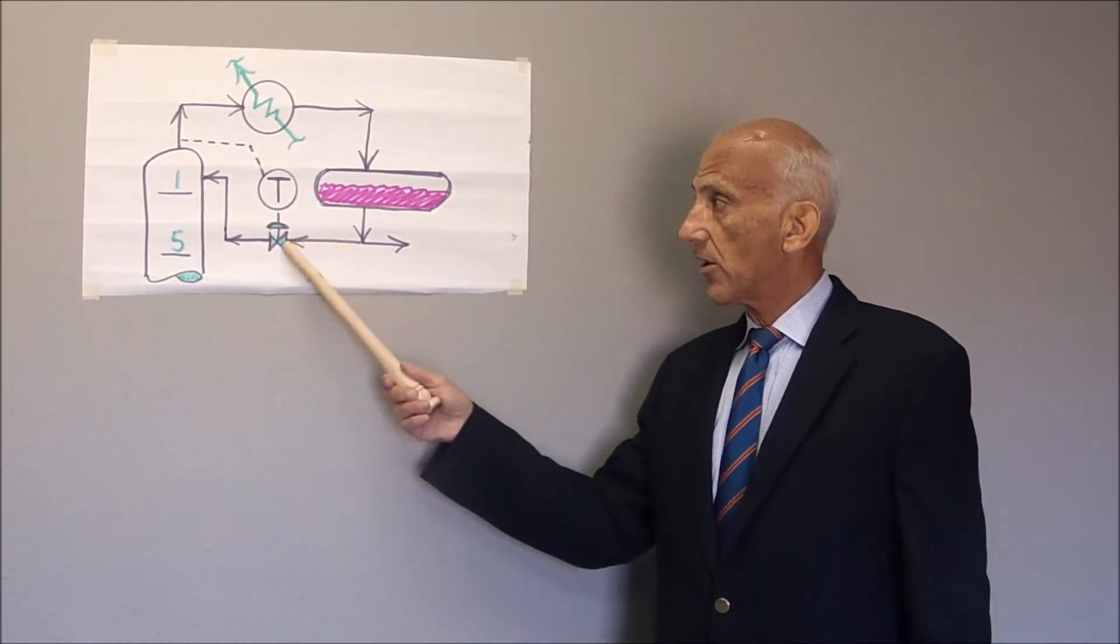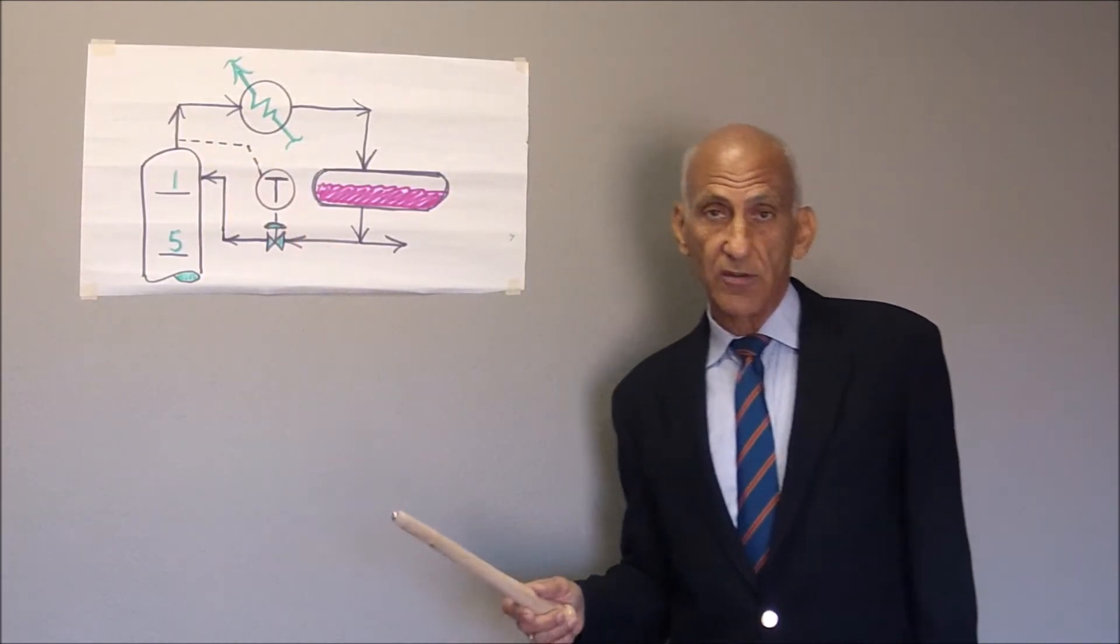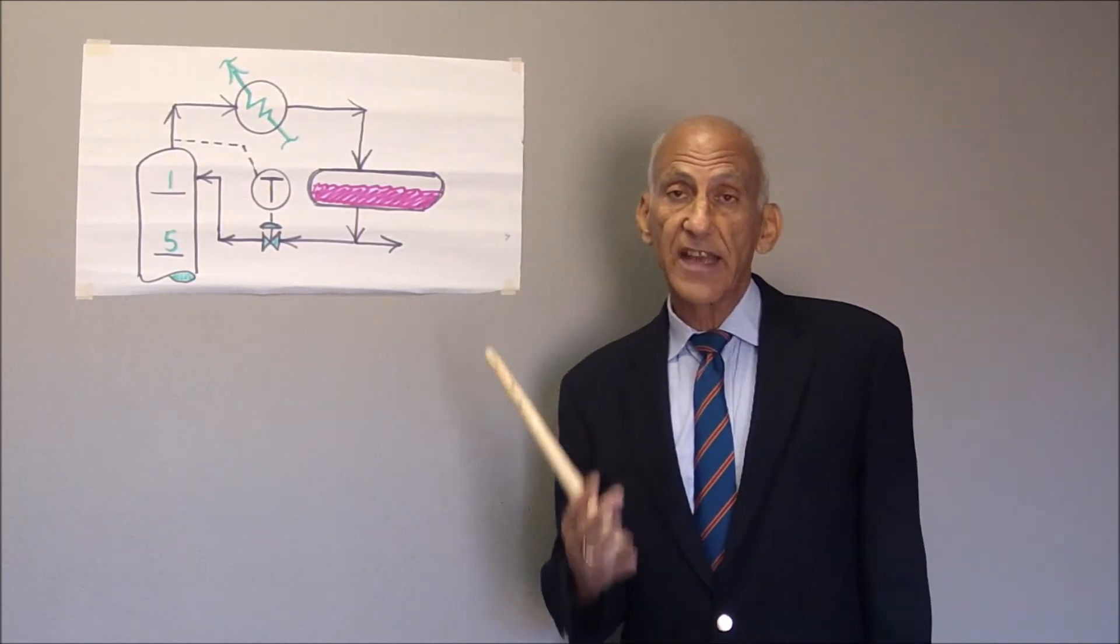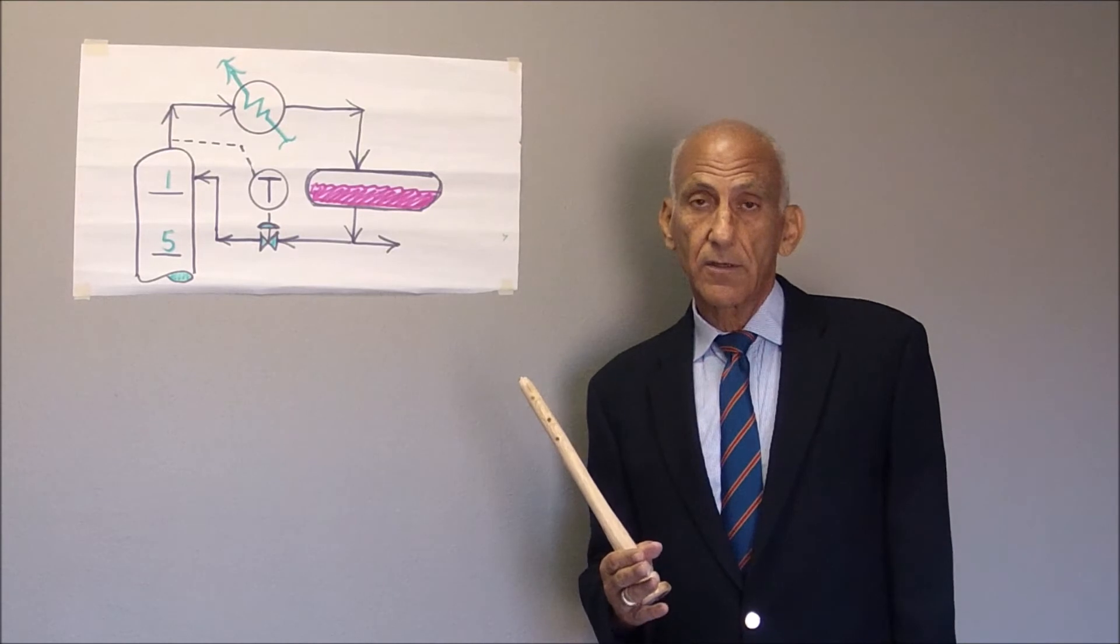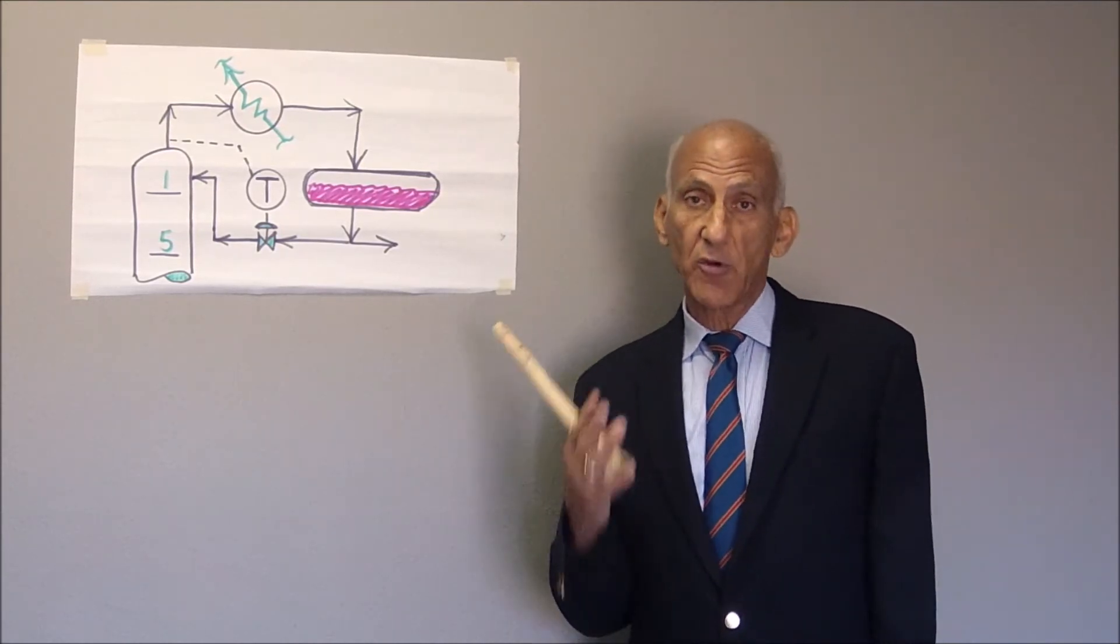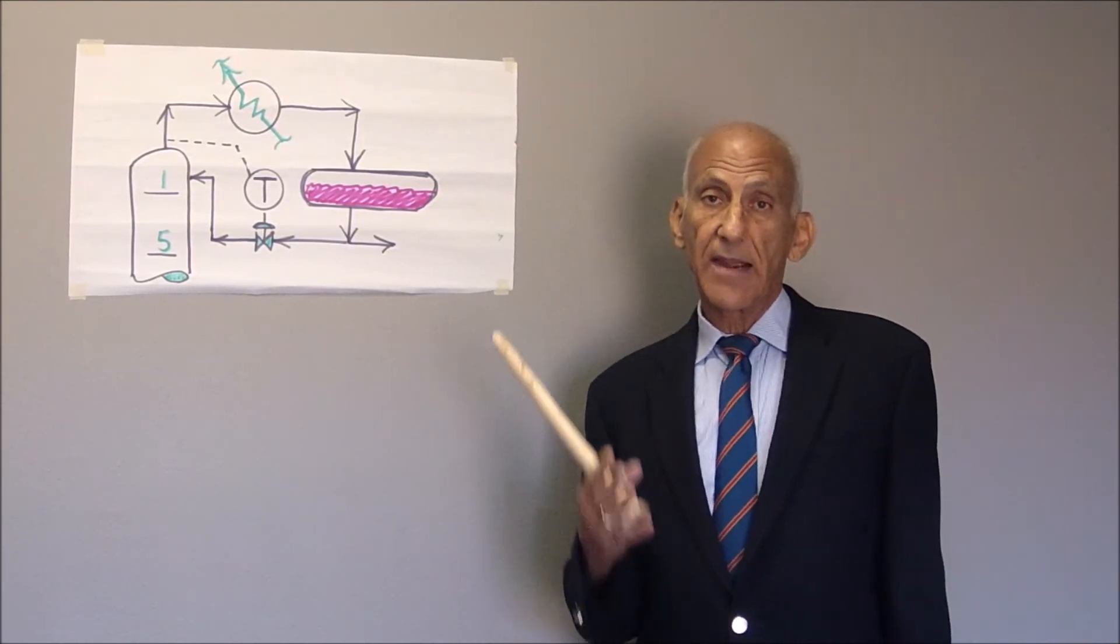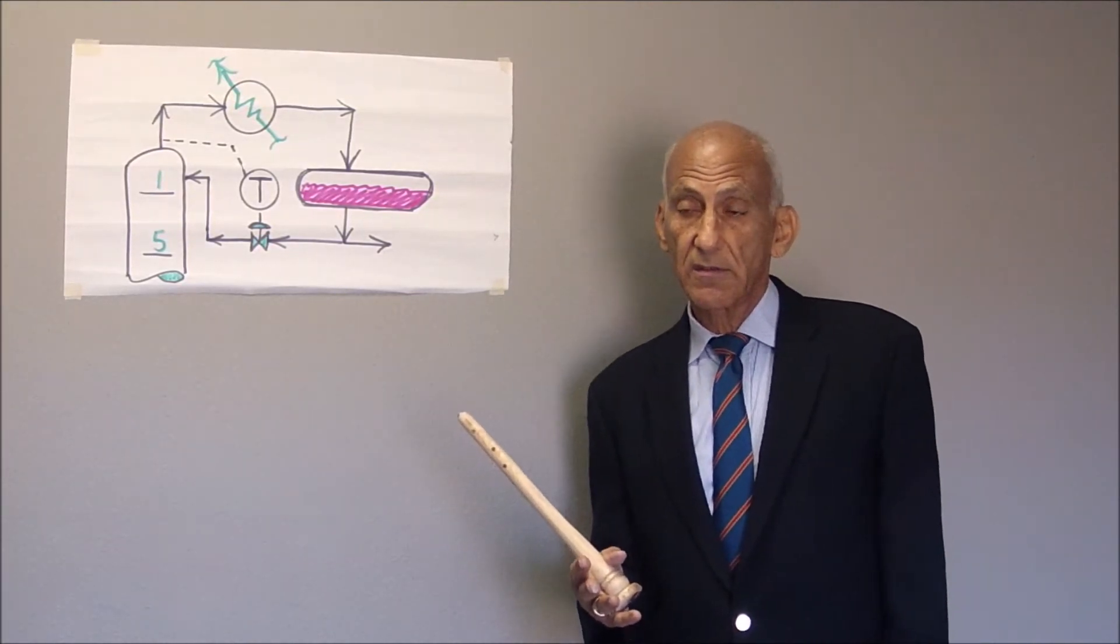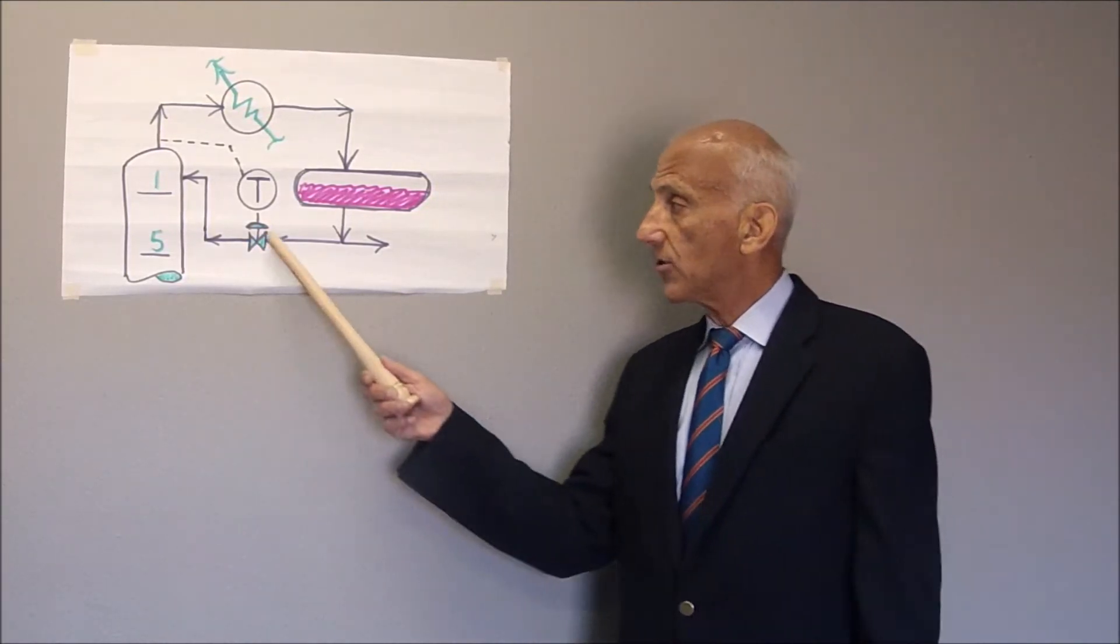However, since we are in automatic temperature control, and since the designer's intent to control the tower top temperature by more reflux, as the tower temperature goes up because of the flooding, because of the entrainment, this valve will open further.